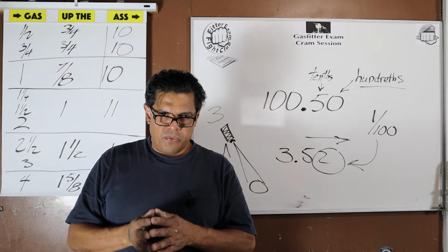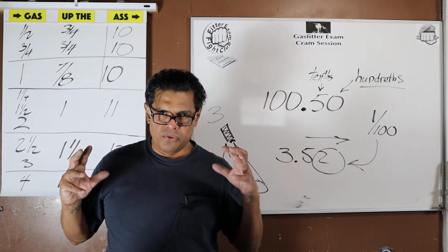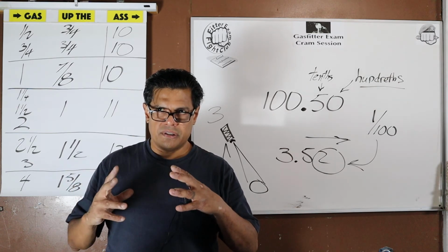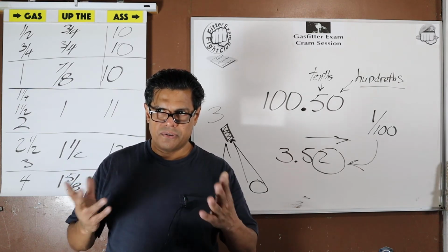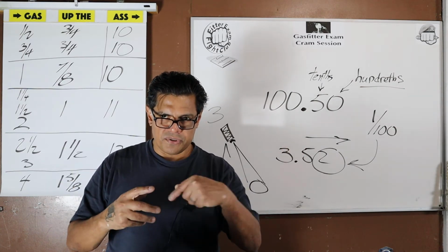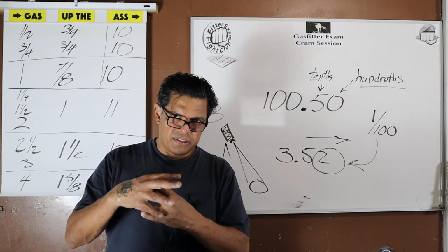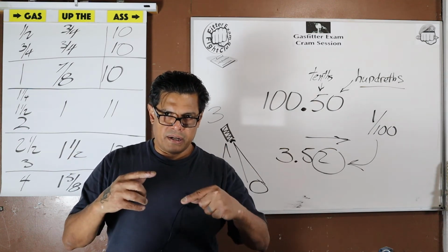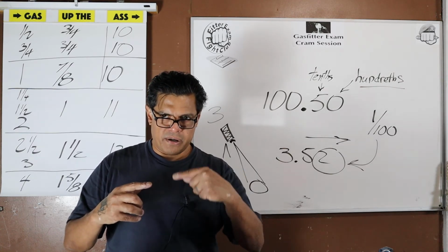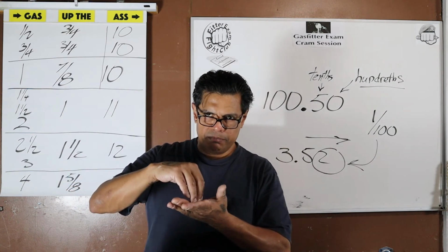Let's say you're working with 2-inch and smaller sizes. You're going to socket weld it, because it's the same thing as when you're soldering copper. You stick the copper into the fitting and then you solder. Well, here you're sticking the steel pipe into the steel fitting, and then you're putting a bead weld at the joint, a fillet weld right at where the pipe and the fitting meet.